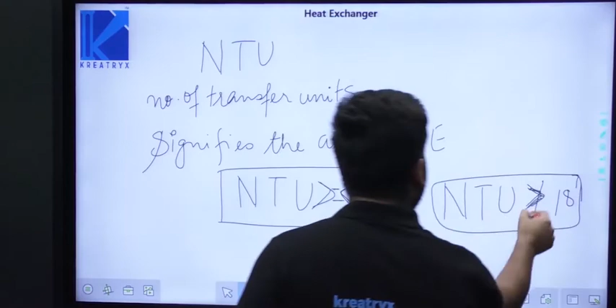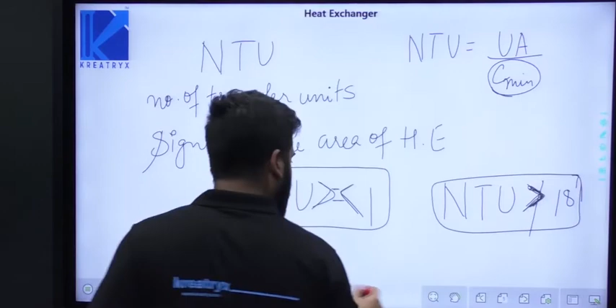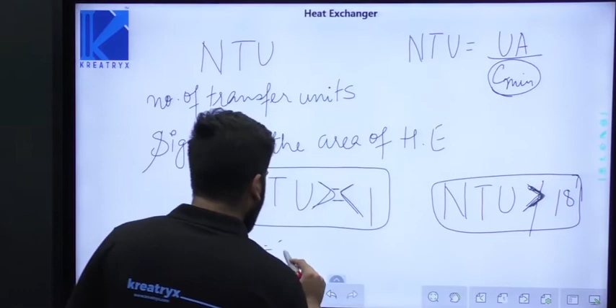However, it can be less than 1, it can be equal to 1, it can be greater than 1, but generally in practical applications it is not greater than 18. So there is a formula that you have to learn for this NTU, which is UA by C minimum. Now what is this UA? U is the overall heat transfer coefficient that you know. A is the total area of heat exchanger that is available for heat transfer between the two fluids. And C minimum is the minimum heat capacity.